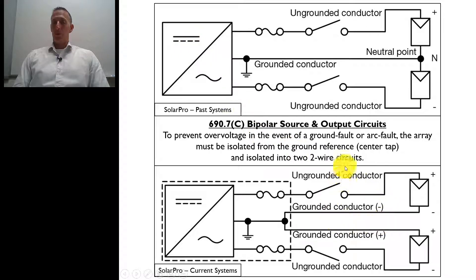Now what they're requiring is that that center, that ground reference or center tap, here's your center tap right here, that this connection is made within the inverter. You can see here's where we're changing it from DC to AC. We're connecting to the earth here.